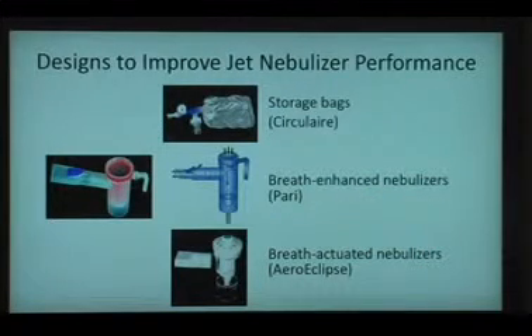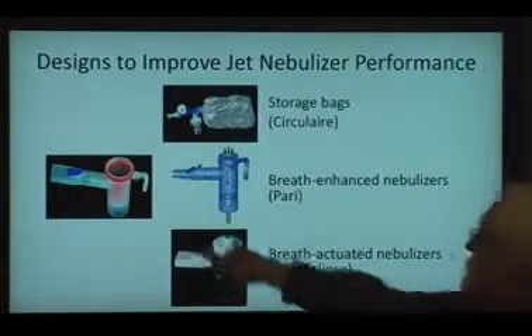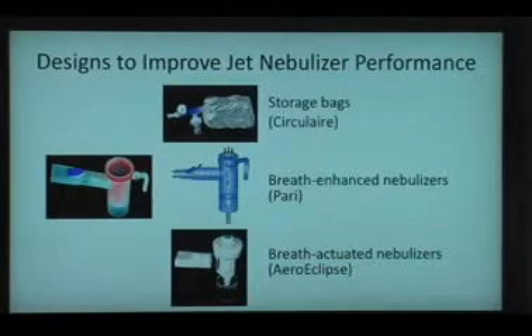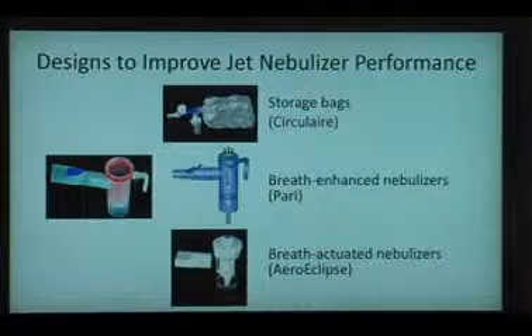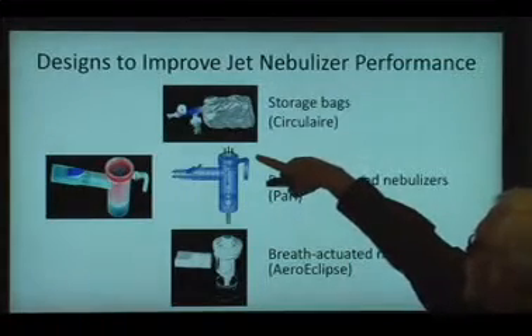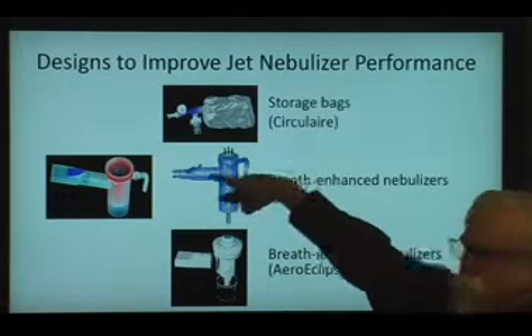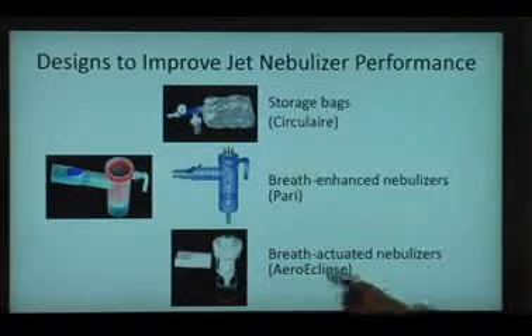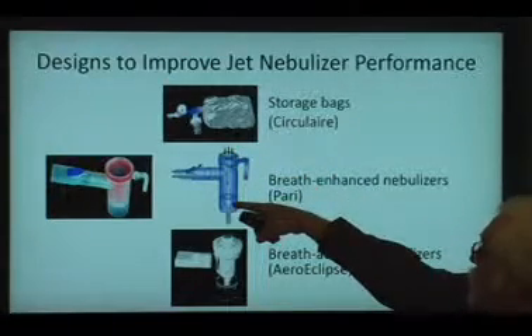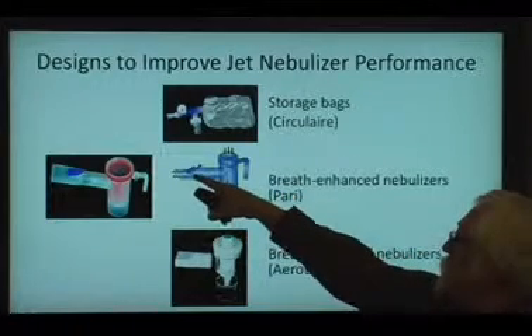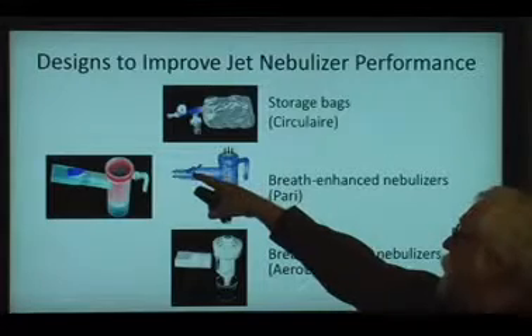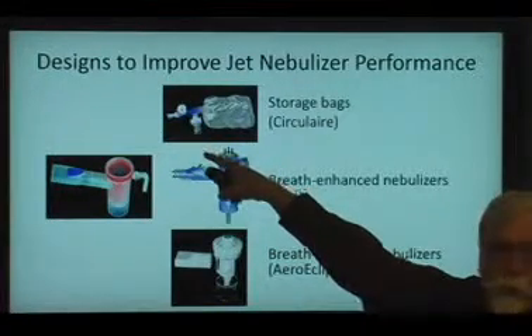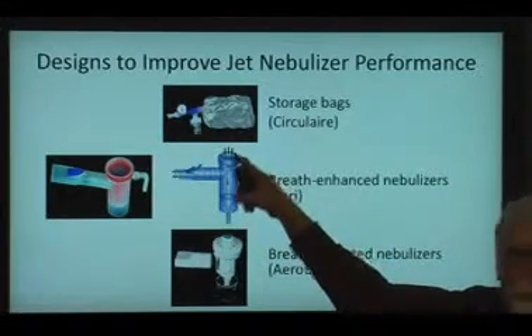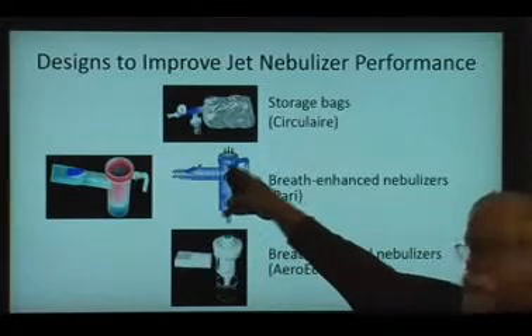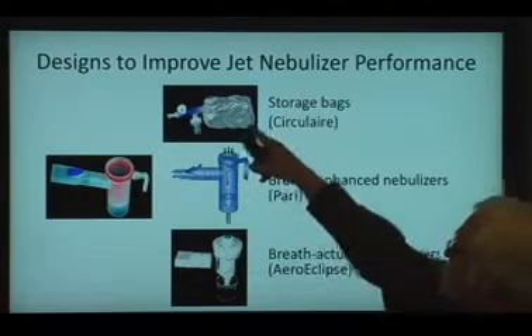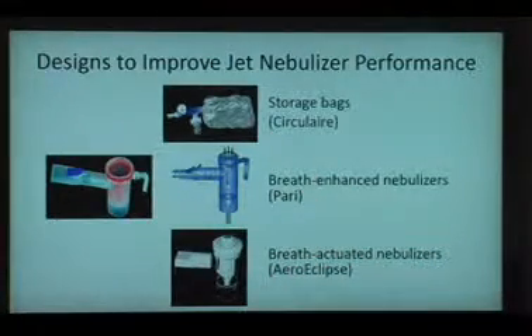There are breath-enhanced nebulizers, which you know as the Pari nebulizer. This is the non-disposable design. The disposable design is the one I think you probably have used more so in the hospital. These are breath-enhanced because during inspiration, during inhalation, the patient breathes through the nebulizer. So this has a mainstream design so that the patient breathes in through the nebulizer, which boosts the output during inhalation, and then there is this opening on the disposable, or the valve on the non-disposable, that opens during exhalation, so the patient does not exhale back into the medication cup and blow the aerosol back out into the room. So the aerosol accumulates in the nebulizer during exhalation, and then when the patient breathes in, it enhances the output because of the mainstream device.